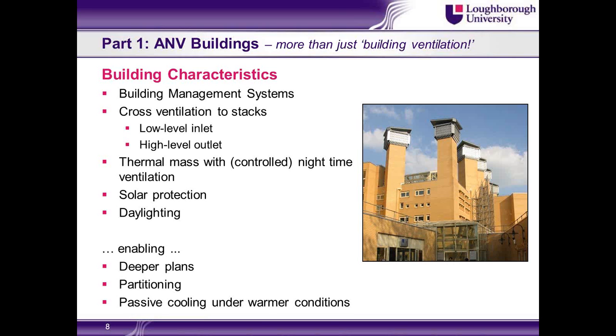Almost certainly there'll be exposed thermal mass with nighttime ventilation for cooling down that mass, solar protection and daylighting. So it's not just about opening a window and allowing fresh air to come in from outside. The strategy won't work if we do that, because natural ventilation can't cope with extremes of temperatures. If we integrate natural ventilation with exposed thermal mass, control, solar protection, and daylighting, like we've got in here, then natural ventilation can be applied to a much wider range of applications and climates. So what this enables us to do is to design for deeper plans, to partition the space up, and I'll show you how we've done that in some of the examples, and to provide passive cooling under warming conditions. And again, I'll show you some examples of what I mean by that.